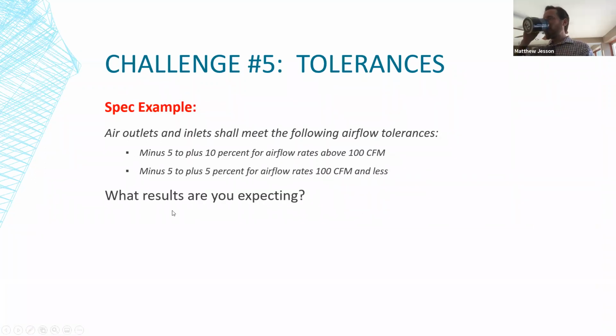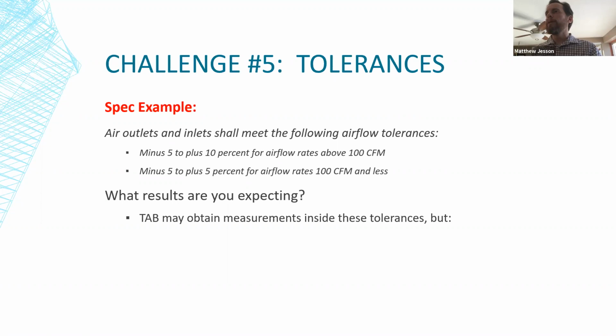So with this particular specification, what are we expecting? Your test and balance agency may be able to obtain measurements that are inside these tolerances, but first of all, it's going to be more time consuming and expensive. You might be surprised at how long it can take you to chase around 5 CFM. So is there value to that? Maybe there is in this particular project, but I think it's something that the engineer needs to consider and maybe discuss with the TAB agency.